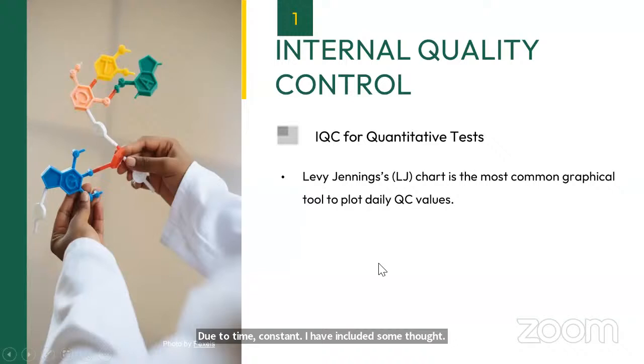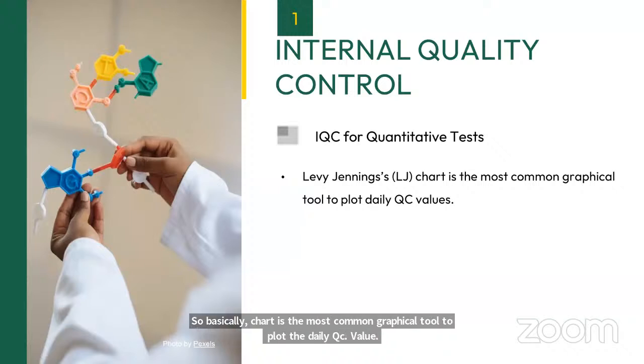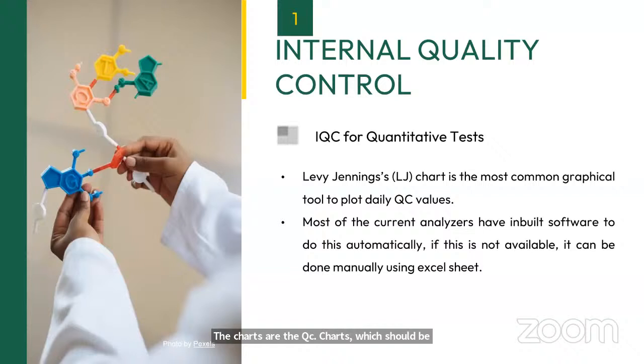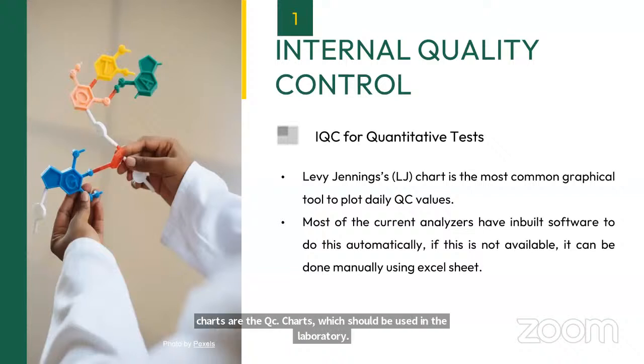So basically, the Levey-Jennings chart is the most common graphical tool to plot the daily QC values. These charts are the QC charts which should be used in the laboratory. Most of the current analyzers have inbuilt software to do this automatically.